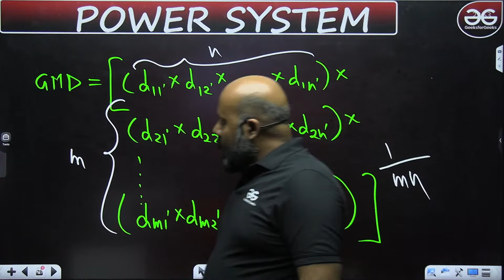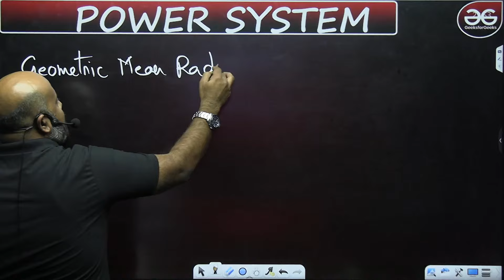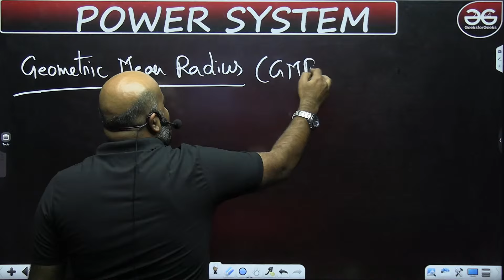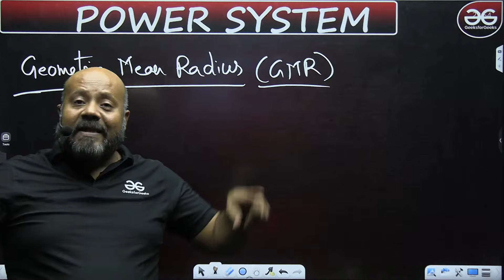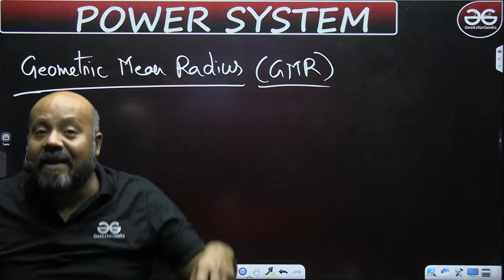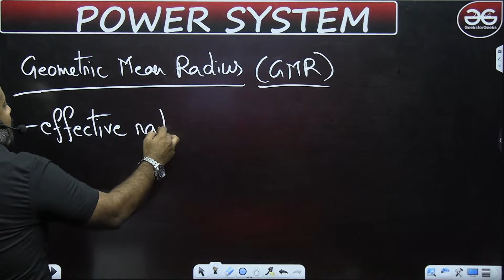Now let us talk about GMR, geometric mean radius. So when I was talking about GMD, I was talking about effective distance between two groups of conductors or two different phases. But when I say GMR, it is always calculated within the same group or within the same phase. It means we are talking about the effective radius.